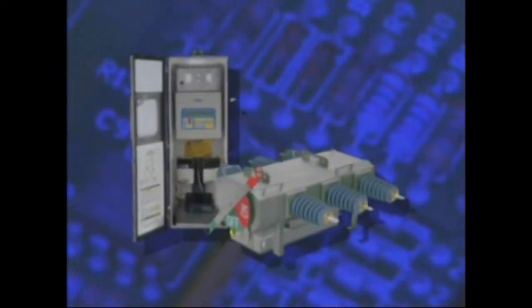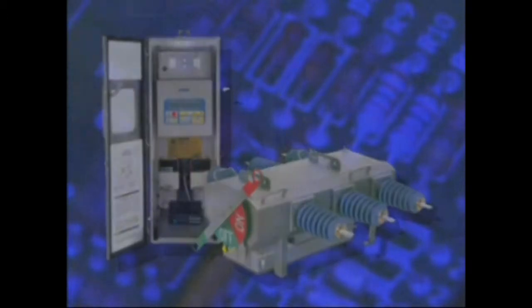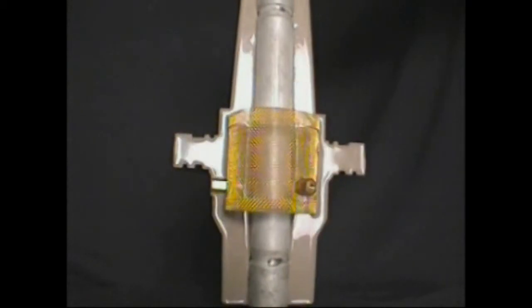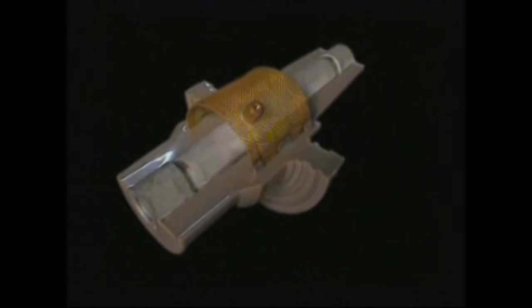Features of the fully automated sectionalizer include current measurement on all three phases using current transformers installed inside the tank. Capacitive voltage transformers molded into each epoxy bushing, providing three phase voltage measurement on both the line and load side of the load brake switch.